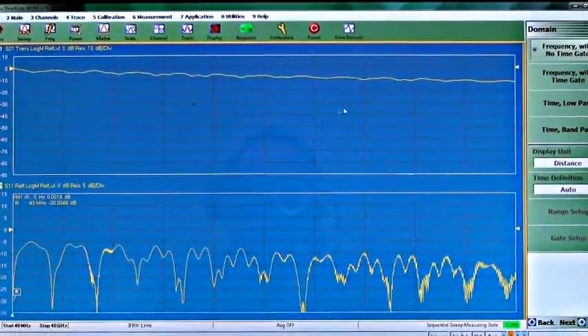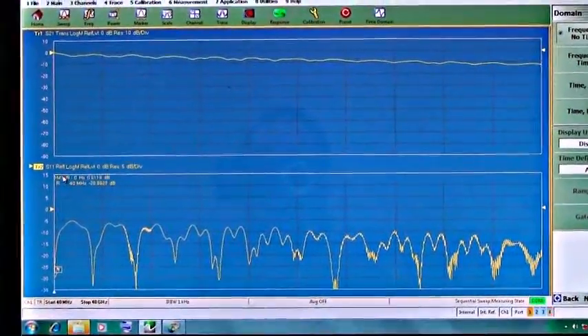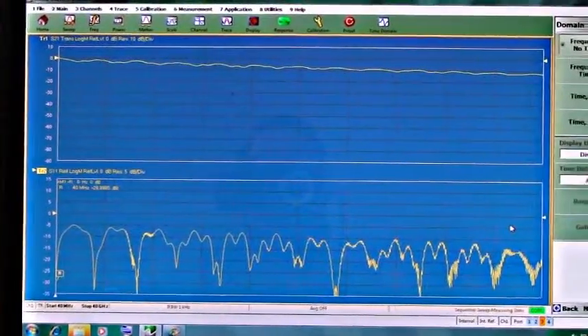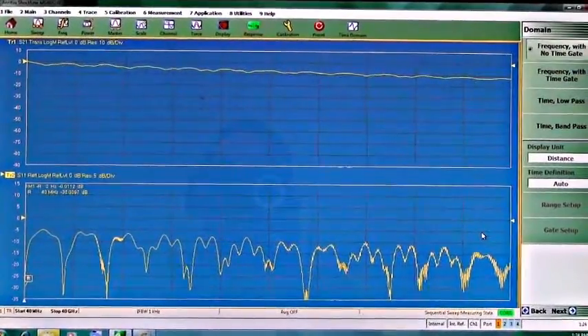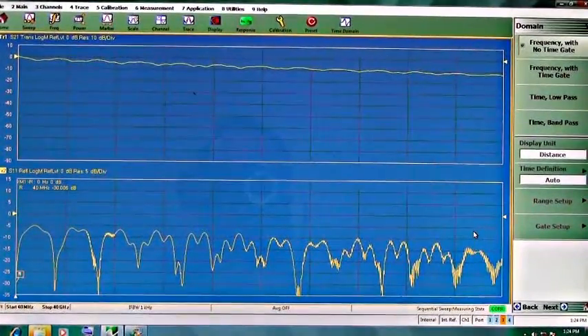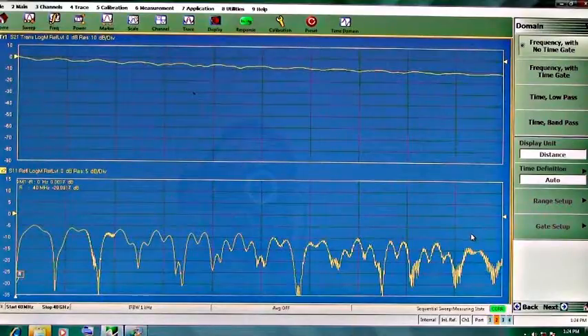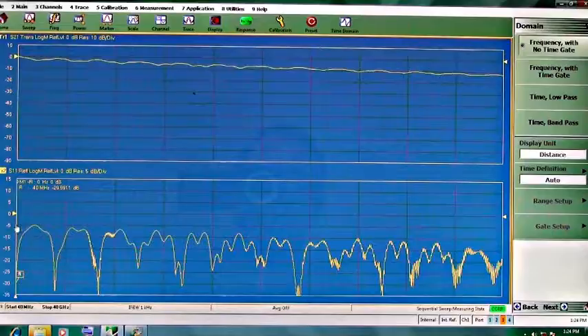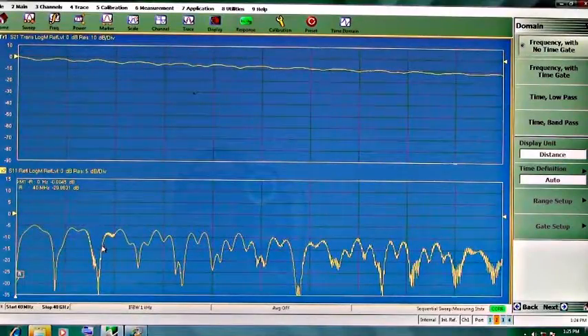Okay, so now we're looking on screen at an S21 measurement and an S11 measurement of a Beatty line. A Beatty line is basically a 50 ohm transition to a 25 ohm transition back up to a 50 ohm transition. So it's in a single-ended mode, and we're looking at S11. That is the basic response of a Beatty standard. Depending on the quality of the Beatty standard, it could be more rounded or less rounded, depending on how well the material has been designed. Anyway, we're going to take a look at it in time domain to see if we actually do get a 25 ohm drop in the impedance.